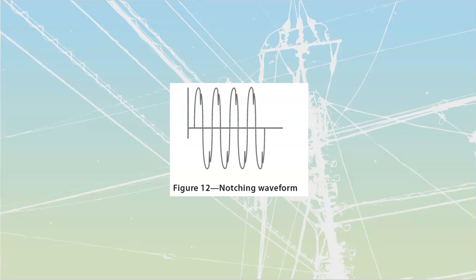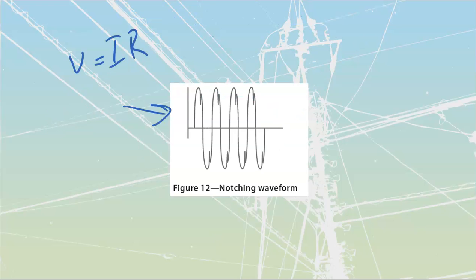This is something we usually see on the voltage system, because V equals I times R. So if I get a rush of current, anytime I get an oscillatory current waveform like this, it usually results in voltage notching that looks like this. Every time we get that current spike, we get a small voltage drop, producing this waveform. It causes problems, but current and voltage are so closely tied together that we usually treat it as one problem.